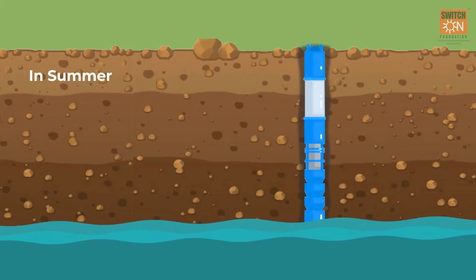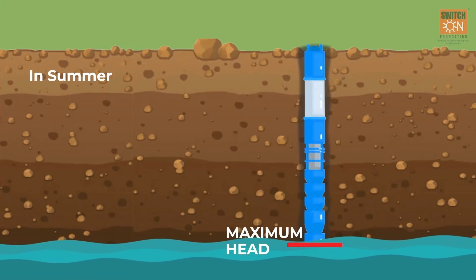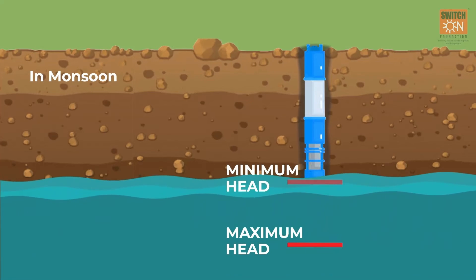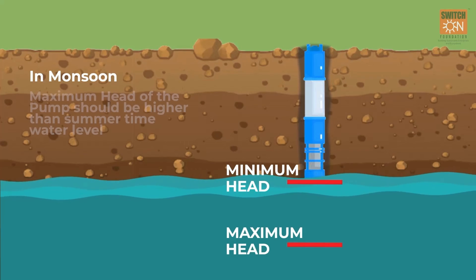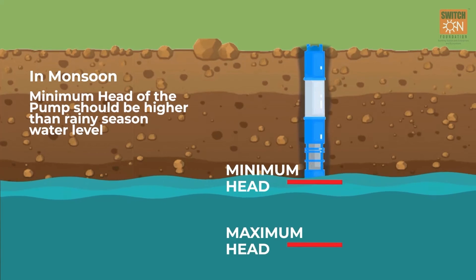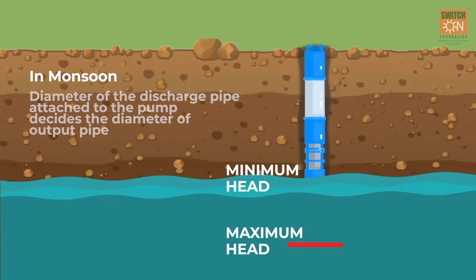Daily average water requirement is considered to decide the sizing of the pump required. In summers, the water level goes down, meaning maximum head, while during monsoons the water level goes up to minimum head. The maximum head of the pump should be higher than the summertime water level, and the minimum head should be higher than the rainy season water level. The diameter of the discharge pipe attached to the pump decides the diameter of the output pipe.